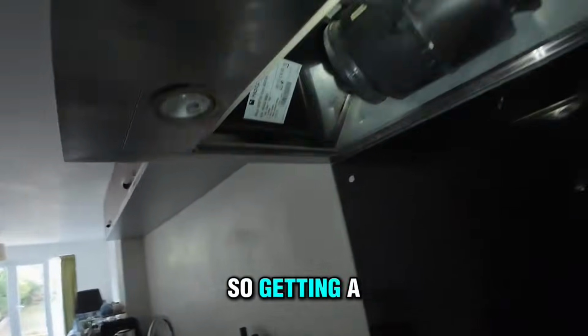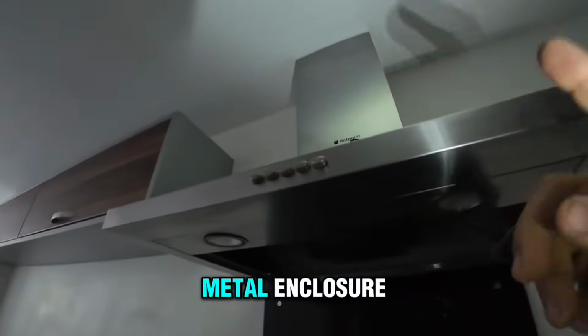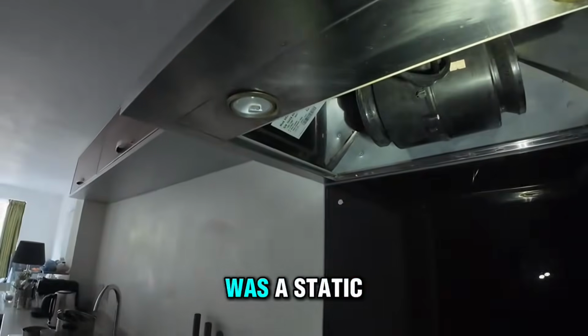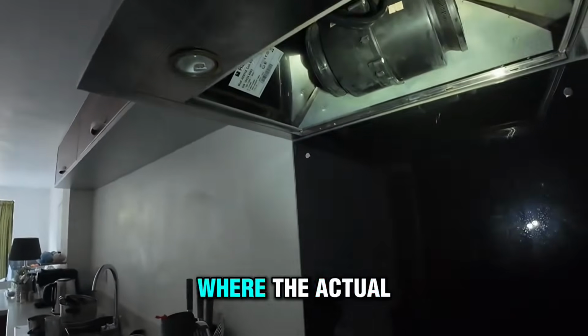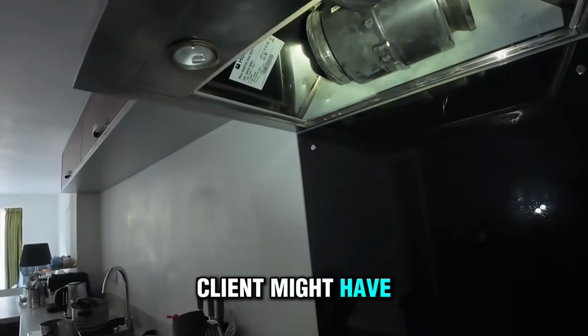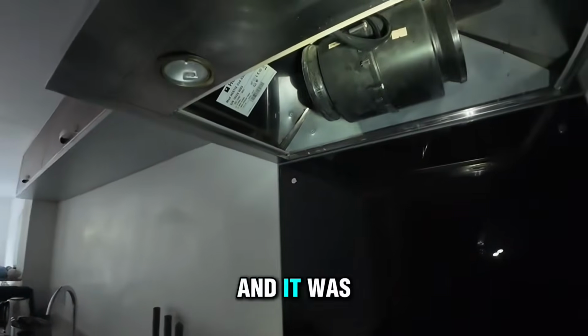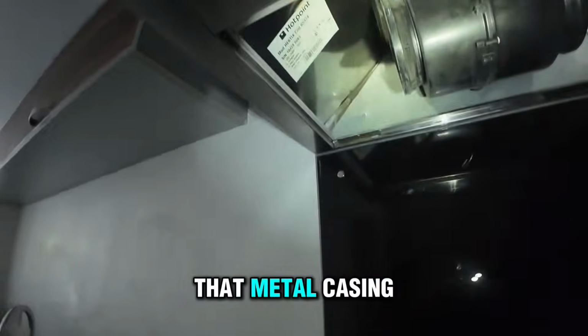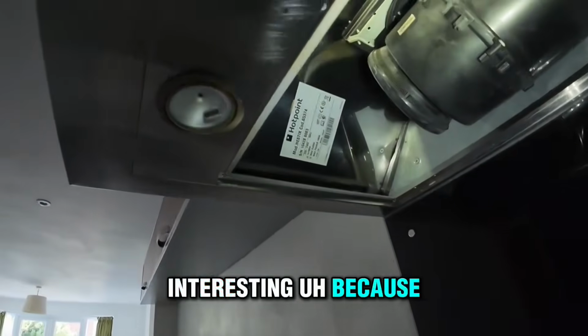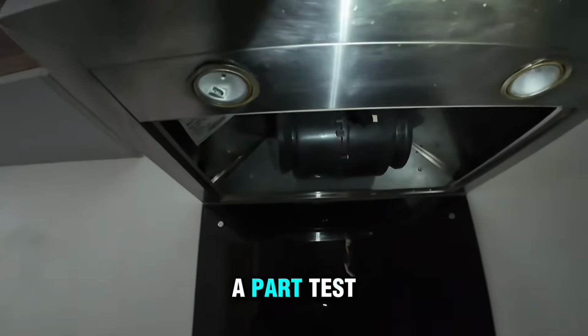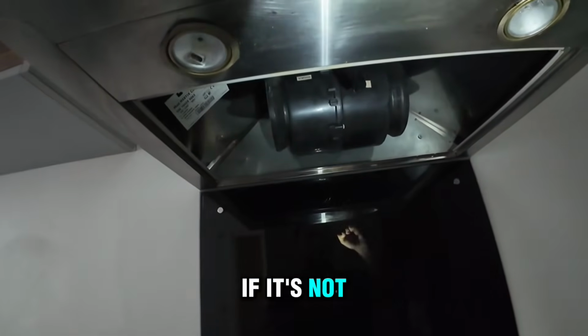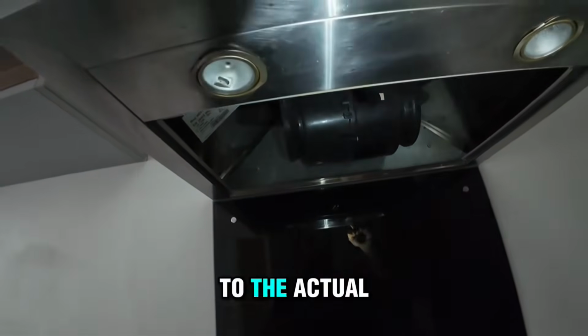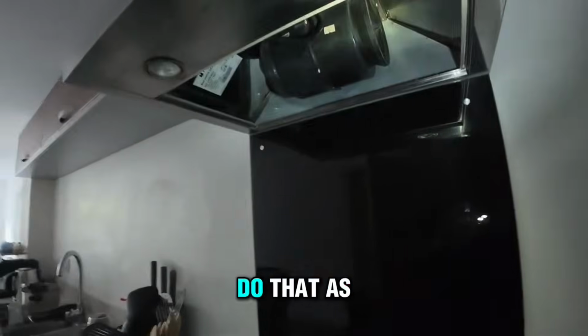So getting a shock from a metal enclosure, I believe this was a static charge. This is where the actual client might have carried the charge and it was just discharged onto that metal casing. Interesting, because it's not connected to earth. I will do a PAT test on this just to double check it's not leaking any current to the actual enclosure. So we will do that as well.